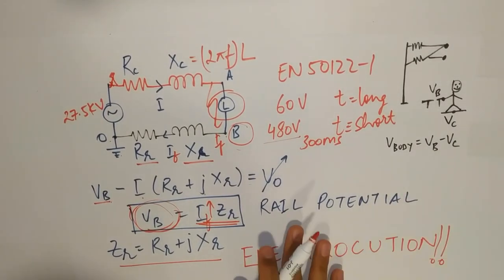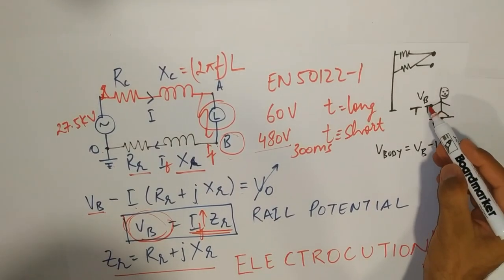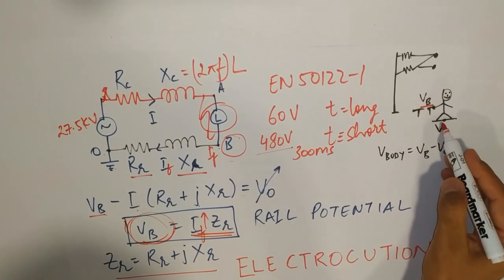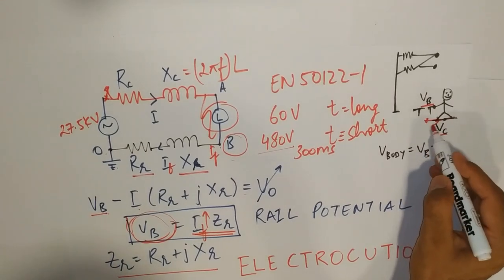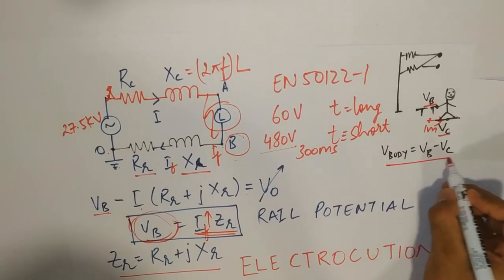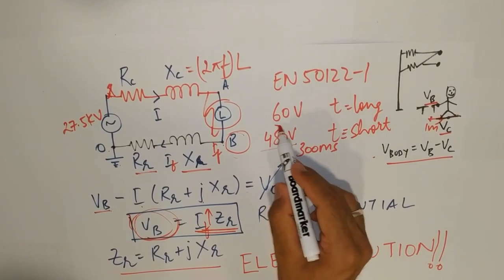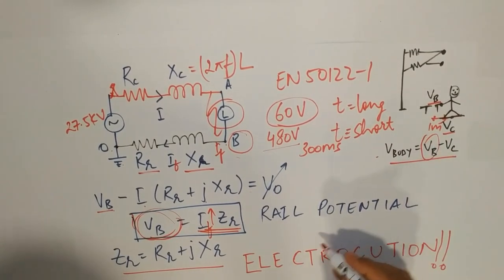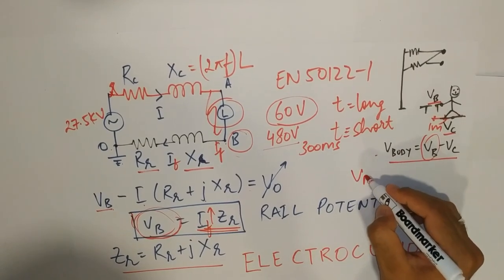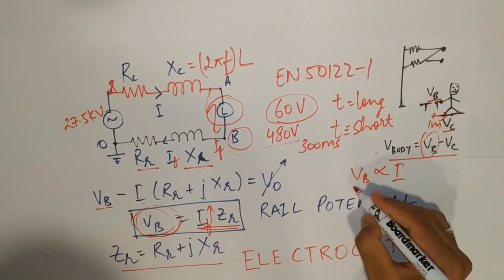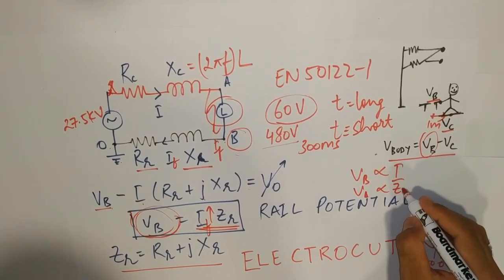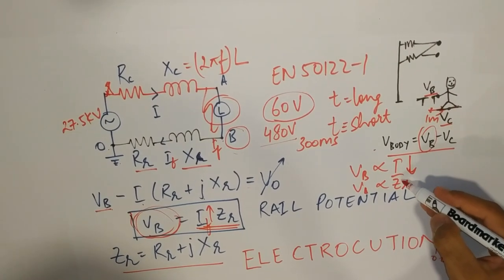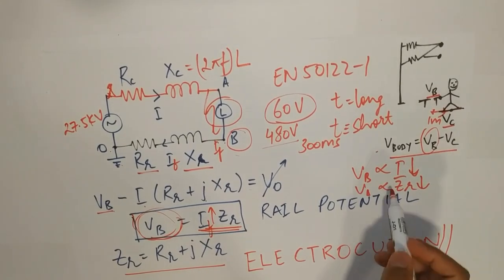Now, what we can do in order to avoid this voltage. See, there is a human being who is trying to touch. A person is trying to touch with his hands to the running rail which is having some voltage VB. And there is some voltage VC where he is standing. We can assume 1 meter apart. So, this will be the voltage across his body. This has to be limited to this voltage value. But what we can do in order to decrease this VB. As this VB is directly proportional to the current. And also directly proportional to the impedance of the return system. So, either we can decrease the current flowing through the running rails or we can decrease the impedance.